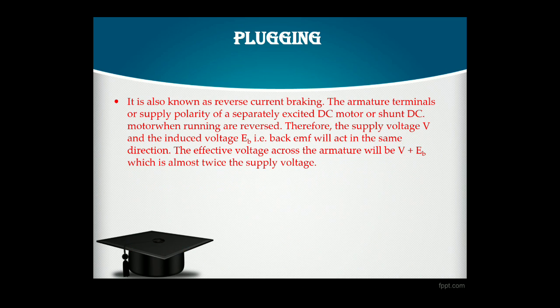Plugging is also known as reverse current braking. The armature terminals or supply polarity of a separately excited or shunt DC motor are reversed while it is running. Therefore, the supply voltage V and the back EMF E_B act in the same direction. According to KVL, the effective voltage across the armature becomes V plus E_B, which is almost twice the supply voltage.